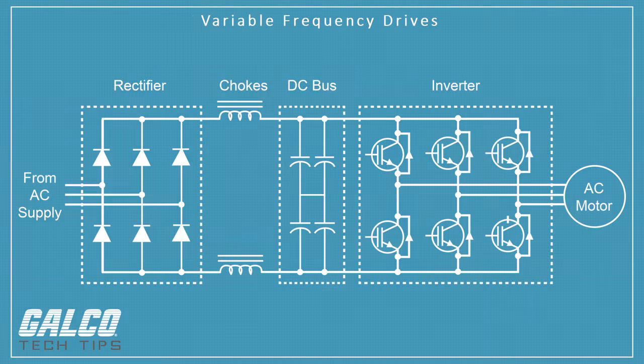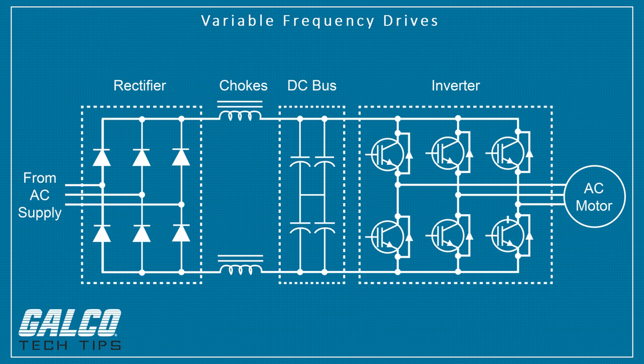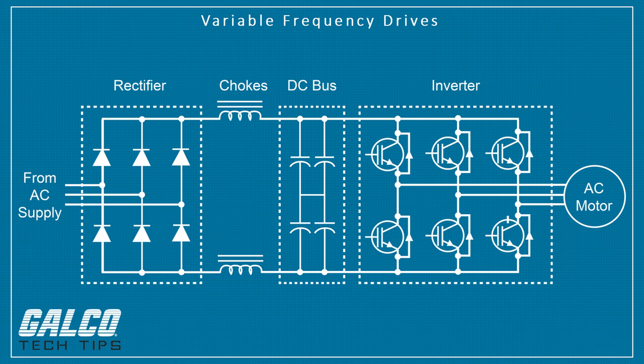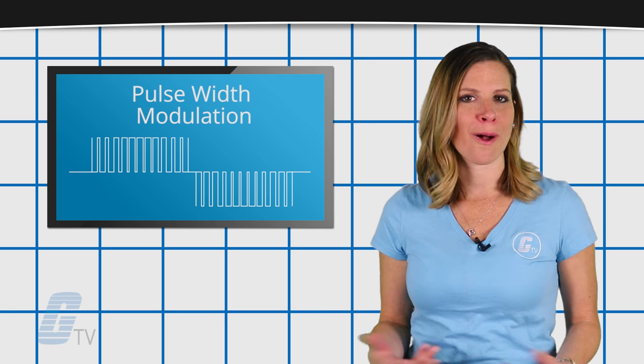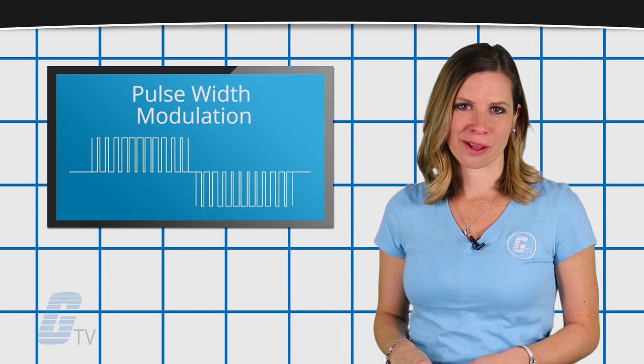These are units that use switching devices known as IGBTs to control the frequency and voltage of the power fed to the motor to control its speed and limit its load through a technology called pulse width modulation.